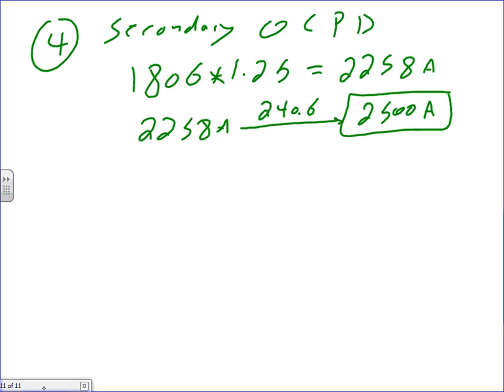And I'm going to do this one, guys. When I do the industrial, because we have panels, we start matching a transformer to a panel. So it's tweaking it to match a transformer to a panel. 250, yeah, I'm sorry. Okay. Why didn't you take that to 450.3(B)? 450.3(A), 1806 times, well, if we're using fuse or circuit breaker. The multiplier is from 450.3(A), not A, circuit breaker then? I'm sorry, no, A. And what's the multiplier there? 125%. Yeah, all right, cool.